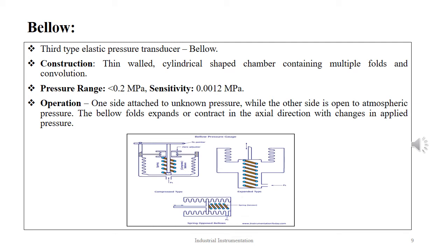In a bellow setup, the unknown pressure is applied at one end while the other end is exposed to atmospheric pressure. The bellow can also be used to measure absolute pressure by evacuating either the exterior or the interior bellow space, followed by measuring the pressure on the opposite sides. Bellows can be connected to potentiometers as well. Bellows are used to measure low pressure, less than 0.2 megapascal, and have a sensitivity of 0.0012 megapascal.